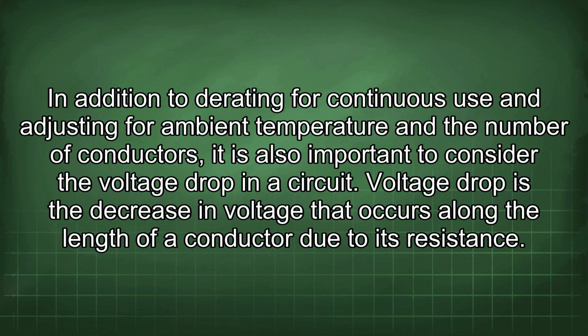In addition to derating for continuous use and adjusting for ambient temperature and the number of conductors, it is also important to consider the voltage drop in a circuit. Voltage drop is the decrease in voltage that occurs along the length of a conductor due to its resistance.